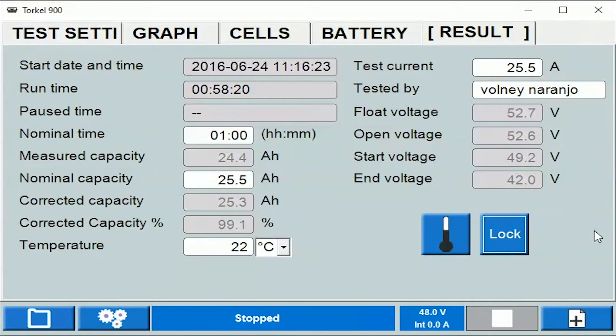Let's go over what each of these fields means. When you do the discharge test, the sequence in which the test is started is: you make all the connections with the charger connected to the battery bank, then you turn off the charger, and then you start the test.